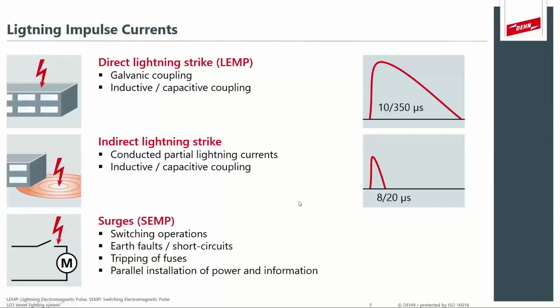Switching surges that come from the utility or switching of loads are also characterized by this 8 by 20 microsecond wave shape. Now, this is the damage that most people experience during thunderstorms. It's actually not a direct strike. A direct strike carries a massive amount of energy, which means that you will have physical damage to your structure or fire and so on, whereas an induced or indirect strike actually just causes a surge in the electrical system, and that's the common case where your television is broken and things like that. It's not actually a direct strike, it's more surge.